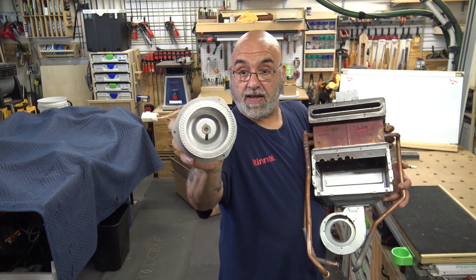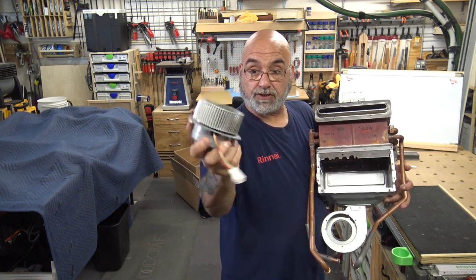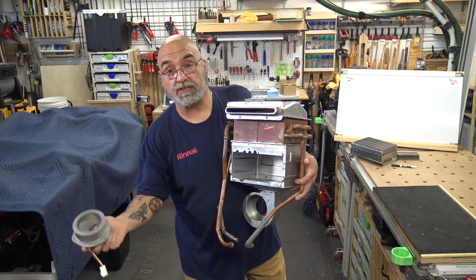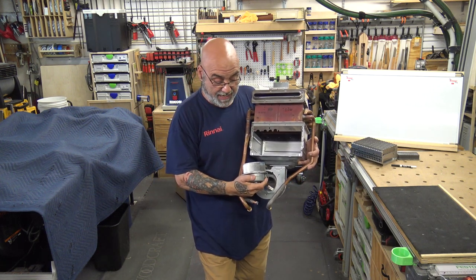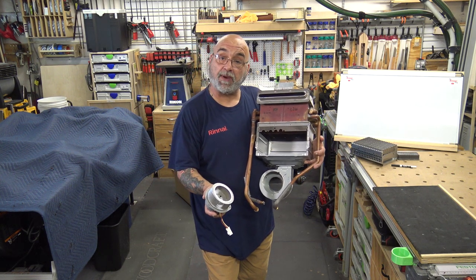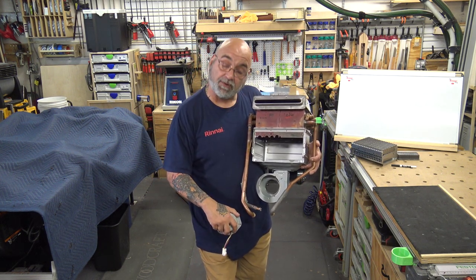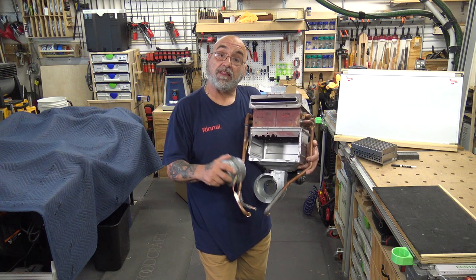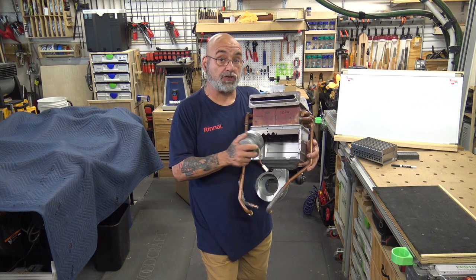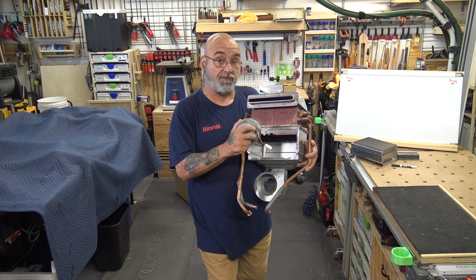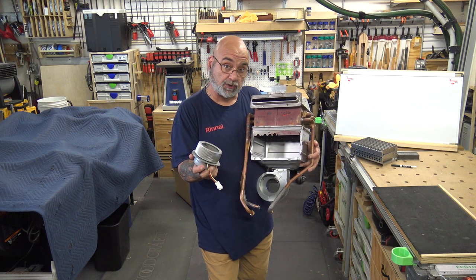One, two, three. Once you remove those three screws, you take it out. You could see, you can actually even leave it plugged in and see if the fan is spinning. Because if you pop the relief valve with this powered up, this fan is going to spin. It's going to try to clear the chamber of gas. So you could see this spin.